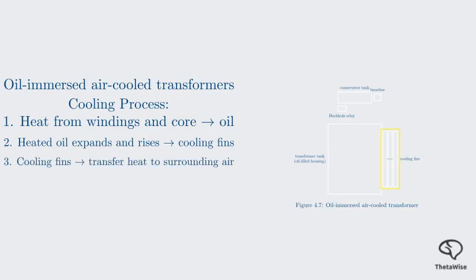The cooling fins are designed to have a large surface area. Here, the heated oil transfers its heat to the cooler ambient air through the fins. Step 4. As the oil cools down in the fins, it becomes denser and sinks to the bottom. It then flows back into the main transformer tank, where the cycle of absorbing heat and circulating repeats. This process is a continuous natural convection cycle, effectively and safely removing heat from the transformer.